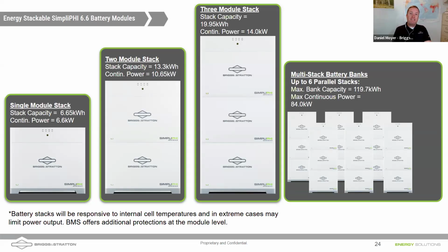But if we're going to talk about that 18K, a 3 stack is only 14, so we're going to be throttling back on the Sol-Ark side on the ability to power load. So if you're going to do an 18K, you're going to need at least 2 stacks of batteries, or 2 controllers — so you could do 2 stacks of 3, or a stack of 3 and 2, whatever the case may be. But I would also think that if you're doing an 18K, you're probably going to want more than 20 kilowatt hours of storage anyway.